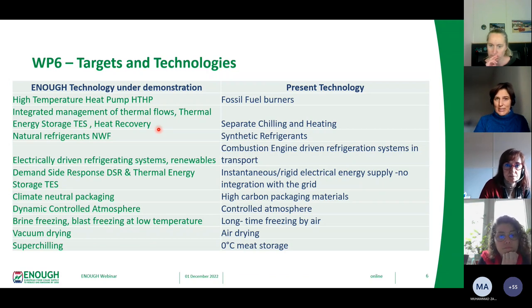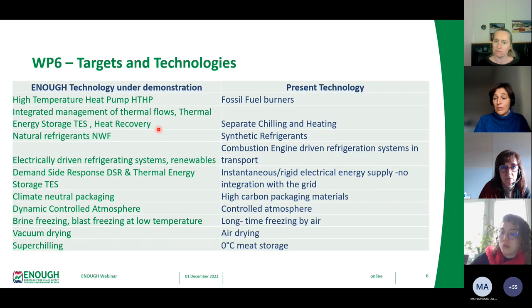to eliminate what is normally happening now in the refrigeration industry, or in the process industry, which is the fact that we have separate chilling or freezing and heating. So we chill, we cool down product, we reject it outdoors, so we waste it, and at the same time we use fossil fuels to heat up warm water or to produce steam. Of course, natural refrigerants can replace synthetic refrigerants in almost all applications of the sector.